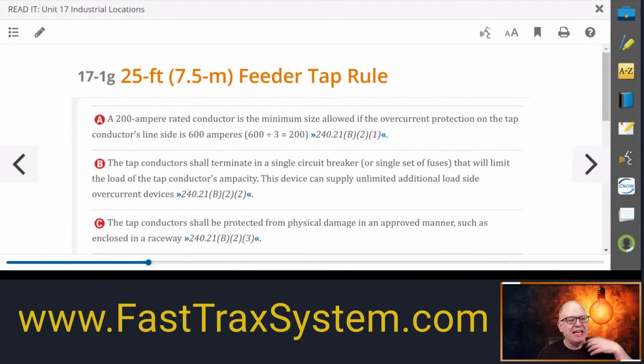Now we'll talk about tap rules. All right. So this is the 25-foot feeder tap rule right here. Okay. So remember last week we talked about the 10-foot feeder tap rule, and we talked about taps in general. This week, I introduced you to the secondary conductor 10-foot rule. Now we're going to be jumping back to the feeder tap rules. And now we're saying, well, can I tap a feeder and can I go up to 25 feet?